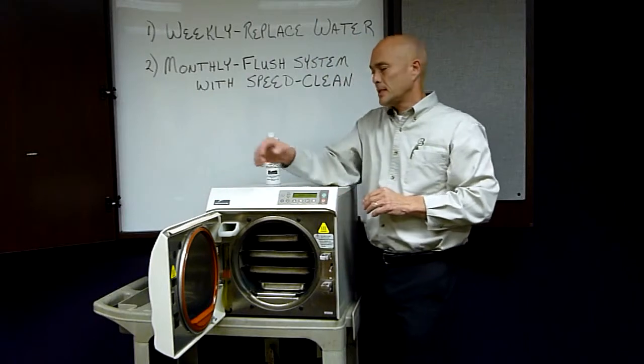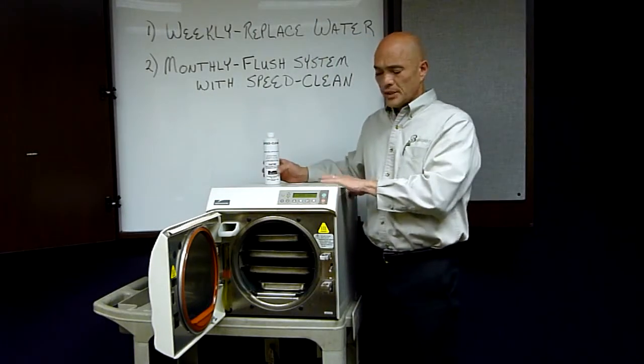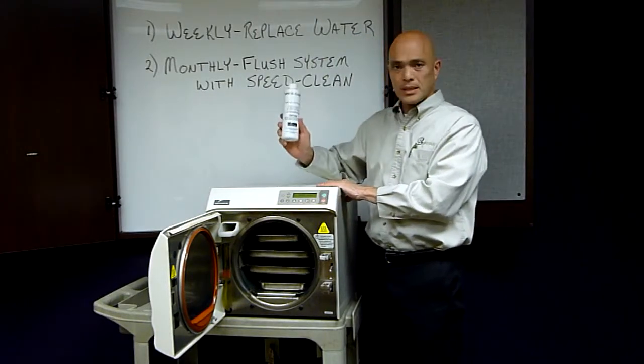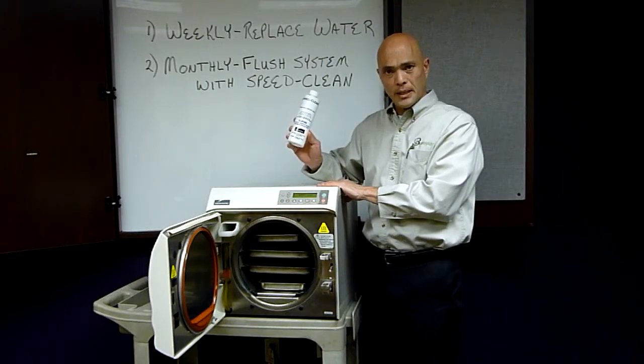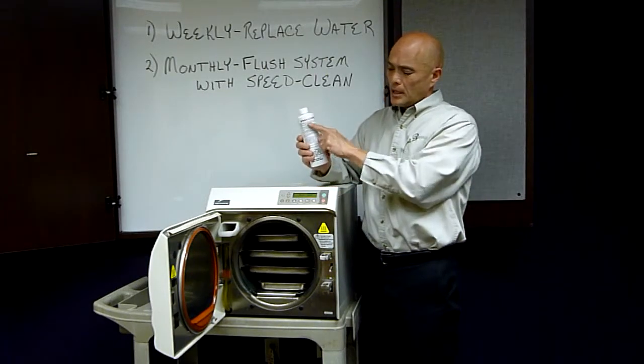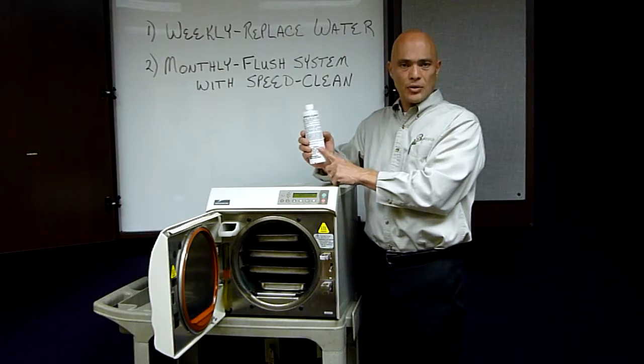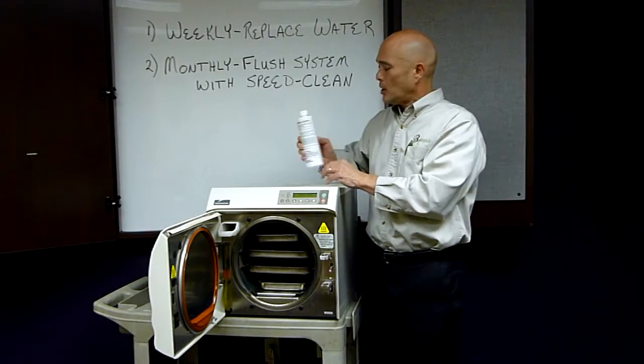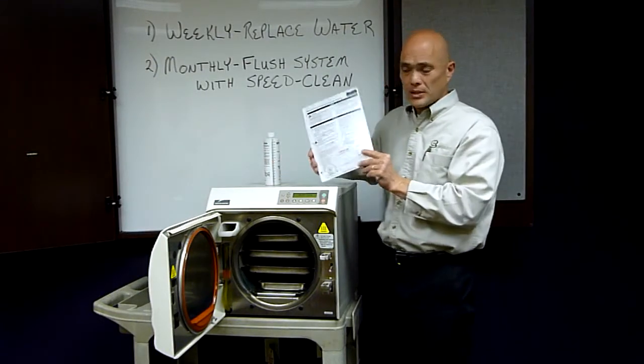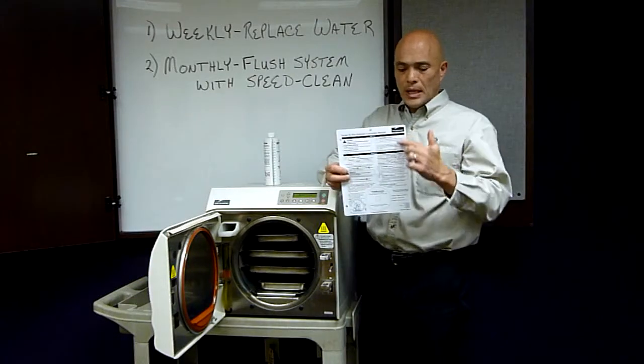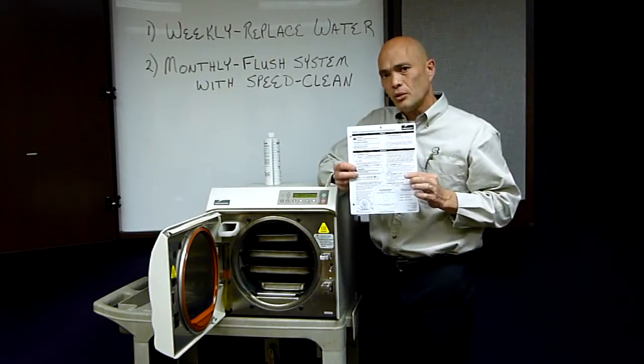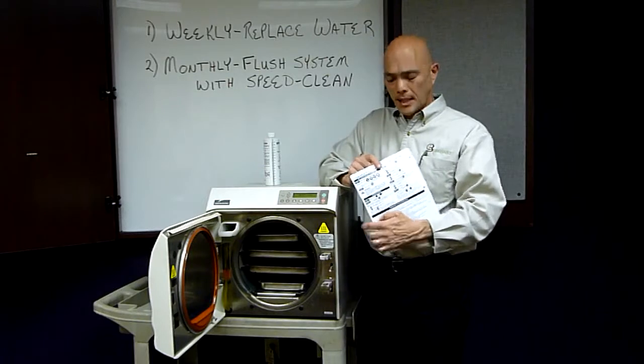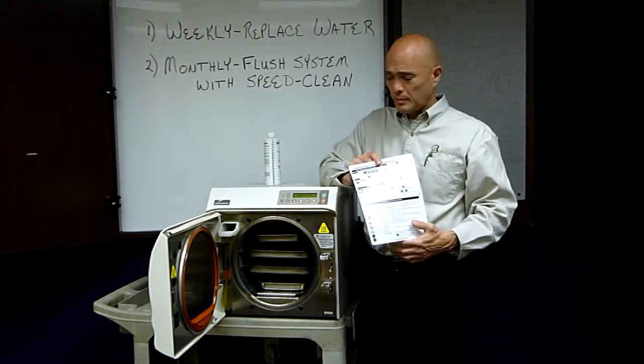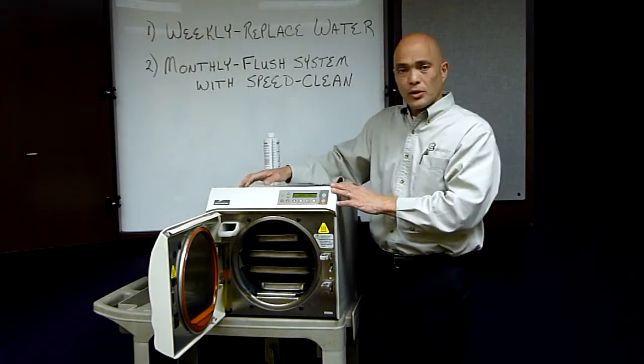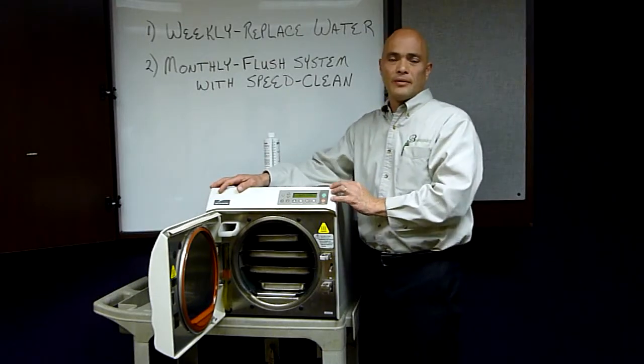On a monthly basis, you want to flush the system, using Speed Clean Sterilizer Cleaner, that's the manufacturer's recommended cleaner. On the back here is very descriptive information on how to go through that process. And also, with all your M11 sterilizers comes this laminated chart. It has your weekly maintenance, your monthly maintenance, and on the back side, it has operation maintenance. That concludes this demonstration on your M11 sterilizer.